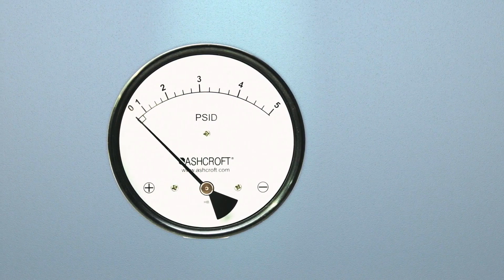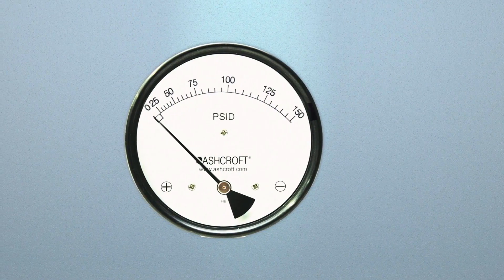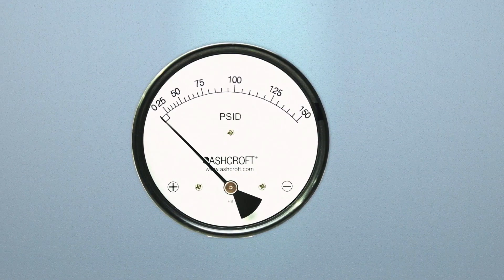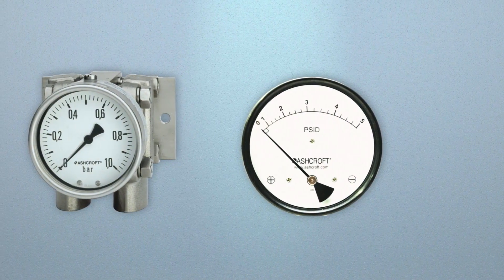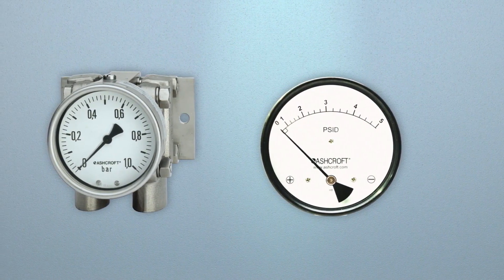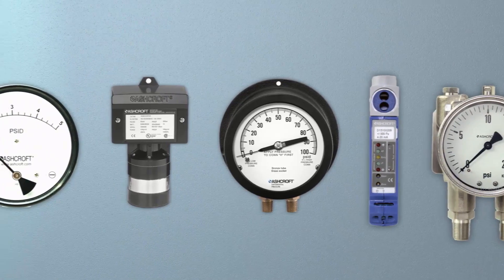When specifying a differential pressure instrument, there are two important factors to consider. The first is the DP range, which is based upon the most difference in pressure that the restriction is likely to produce. The second is the instrument's ability to contain the line or static pressure level.